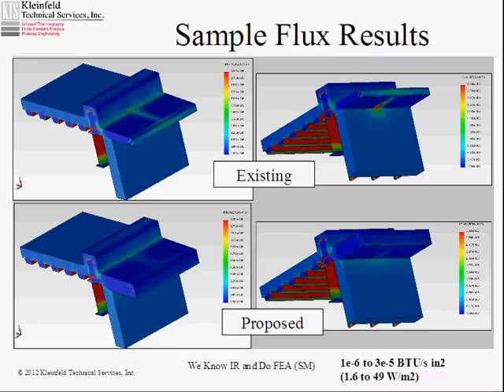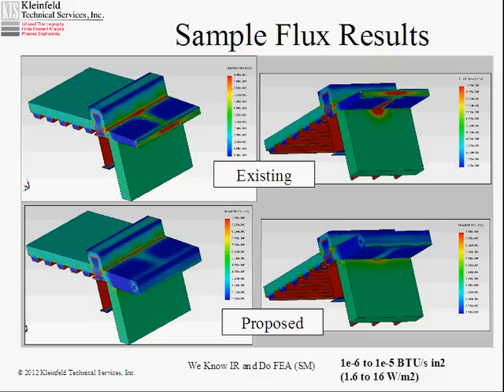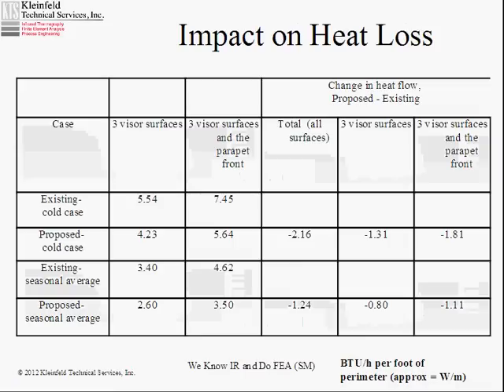This is a comparison of the existing and proposed. These are flux results in BTUs per second per inch squared, or watts per meter squared. You can see there's a significant loss in the existing, and not so much in the proposed. The design changes resulted in a considerable reduction in flux from the surfaces. Looking at a tighter span, you can see more clearly what's going on. There is a loss on this edge even in the proposed — part of it is difference in boundary conditions between the front and the bottom. The bottom sees the ground as a radiation target; the front sees the sky as a radiation target, and those are two significantly different target temperatures.